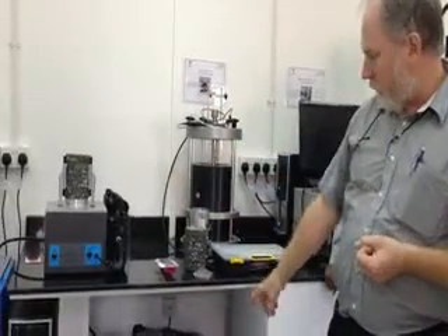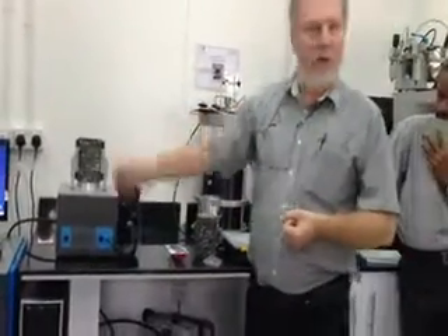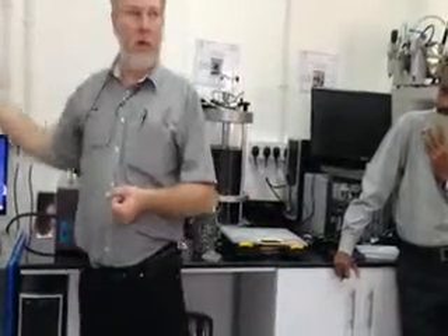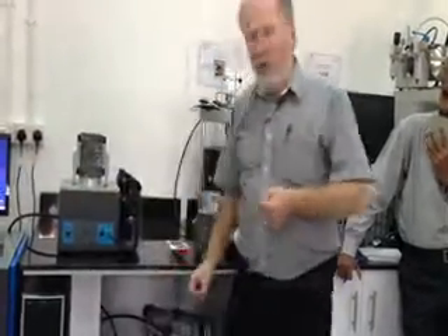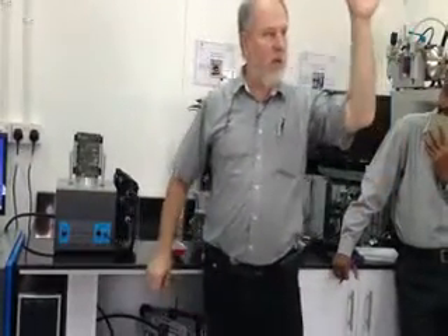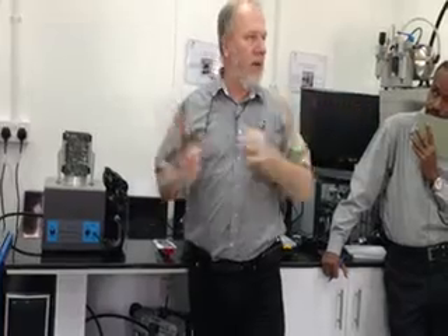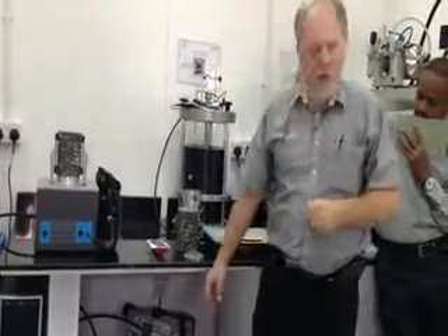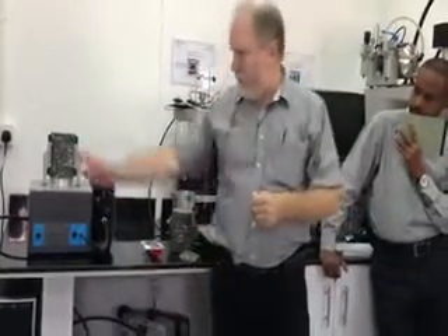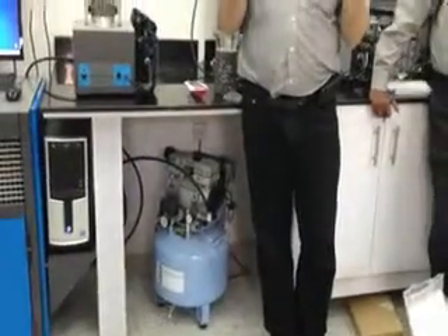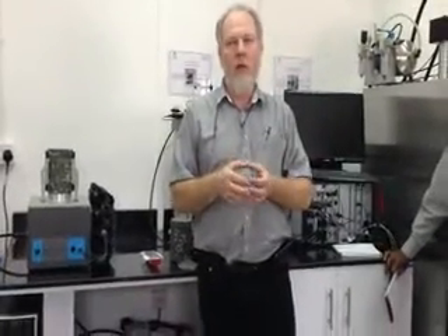For this system, you typically need some air for the confining pressure for raising the cell. At the moment, there was meant to be a compressor set up for the lab here, but we've got this small compressor we can use for testing. It's sufficient to run an AMPT, because if you're doing any confining pressure tests, the specification only, I think, has a maximum of 210 kPa cell pressure.